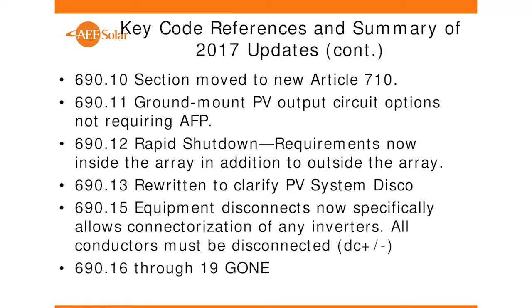Now, when we talk about arc fault protection on large-scale plants, Article 691 says that if you're not going to comply with 690.11, you've got to have some type of an engineered plan for how you're going to address arc faults in a PV array. And there are various ways of doing that. But as arc fault protection continues to mature, even the largest of systems will probably incorporate it regardless of the requirement. Rapid shutdown requirements are now inside the array in addition to outside the array, so we can talk about that a little bit as we finish up this afternoon.